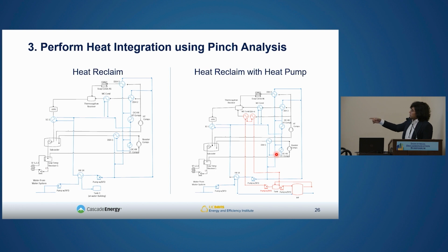For our heat pump system, we again use the refrigeration system as source, using a water-cooled condenser and a de-superheater to isolate our heat pump from the refrigeration system. We've also added strategic storage opportunities for both our heat pump and heat reclaim solutions, so the plant can operate these systems independently and store heat when extra is available, using it when waste heat is low.